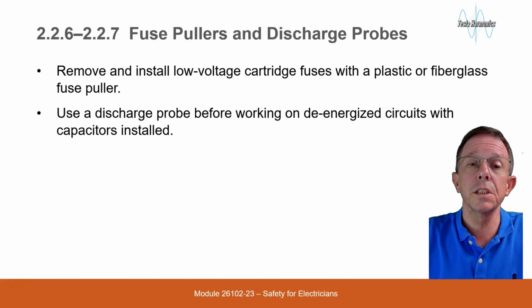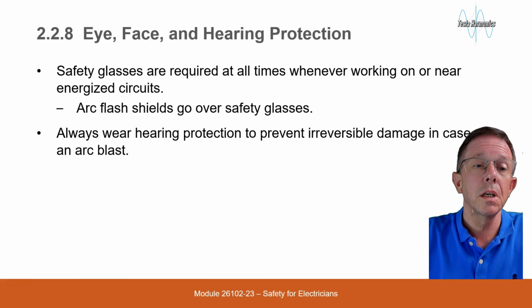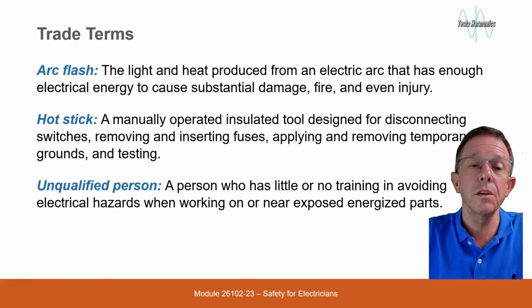Fuse pullers and discharge probes. Remove and install low voltage cartridge fuses with a plastic or fiberglass fuse puller. Use a discharge probe before working on de-energized circuits with capacitors installed. Eye, face, and hearing protection. Safety glasses are required at all times whenever you're working on or near energized circuits. Arc flash shields go over safety glasses. Always wear hearing protection to prevent irreversible damage in the case of an arc blast.